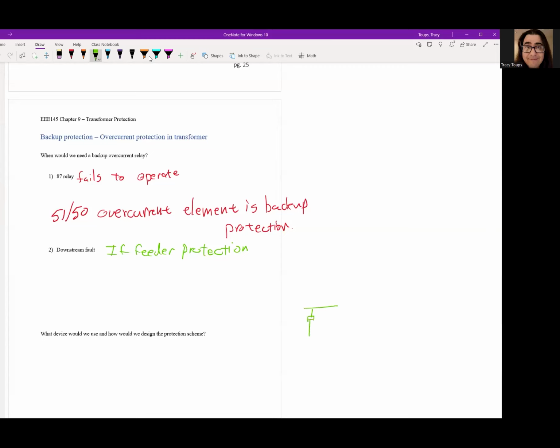right? So we'll have a breaker, we'll have our feeders down here. This is a low voltage bus. We will then go to a transformer right here. And we'll probably have a circuit breaker here. We might have a circuit breaker down here, right? There would be some type of 50-51 element over here, right? This transformer 50-51 element will back up the feeders on the low voltage side because they're more downstream. These are feeders down here, okay? So if the feeder protection fails, the transformer 50-51 acts as a backup protection.